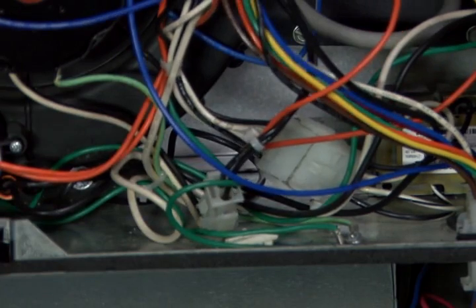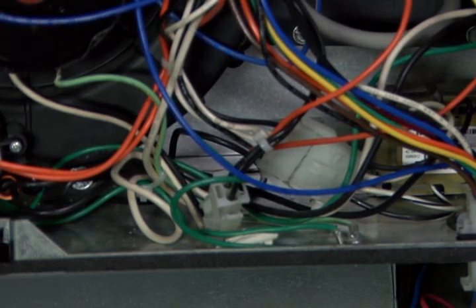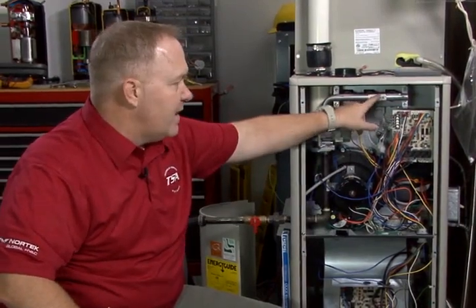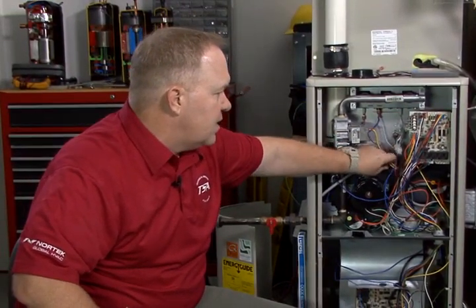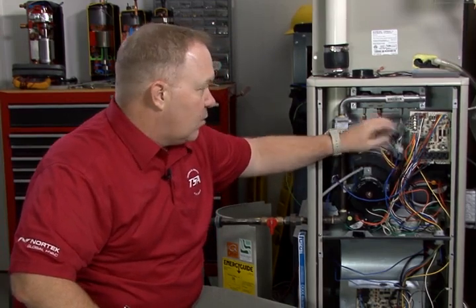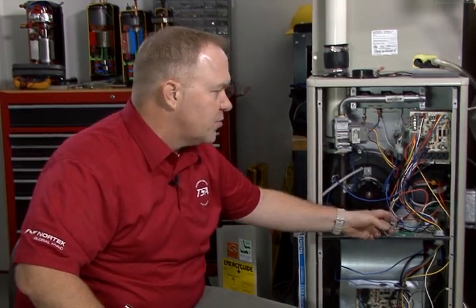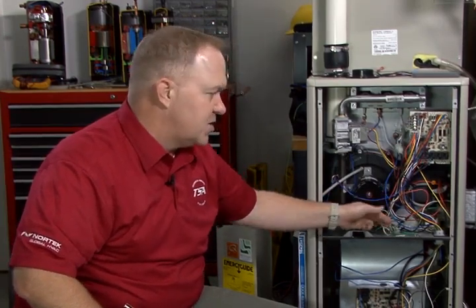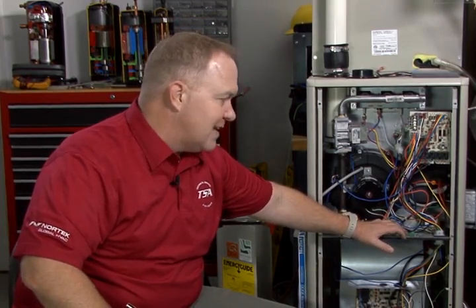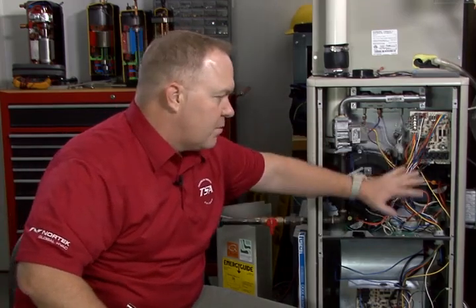You have to have a proper earth ground in that circuit. The board goes back to earth ground, if you will, and part of the importance of that ground is that this is the process that the control board uses to prove and rectify flame. As an example, on a gas furnace, when that furnace fires, it begins to travel back through the flame sensor, or it's emitting off of the flame sensor, traveling back through earth ground, and the board is also grounded to chassis. It's very important that you know that you have a proper earth ground in that circuit that supplies the furnace so that the remainder of the electronics in the furnace will benefit from that.